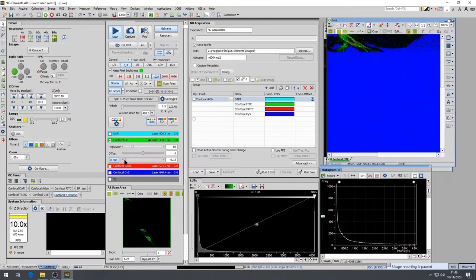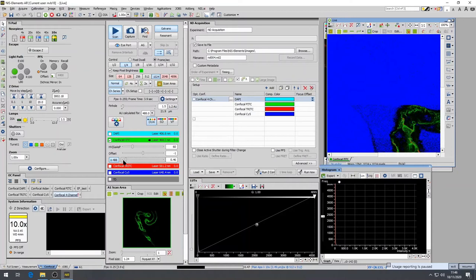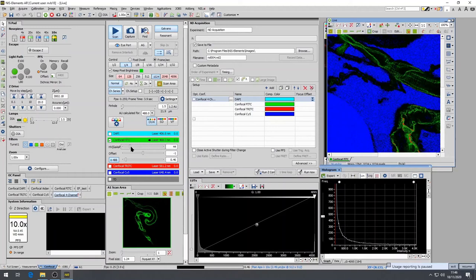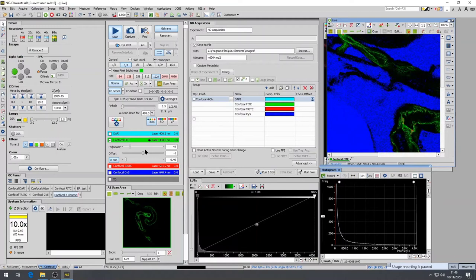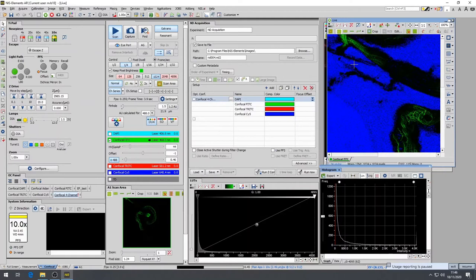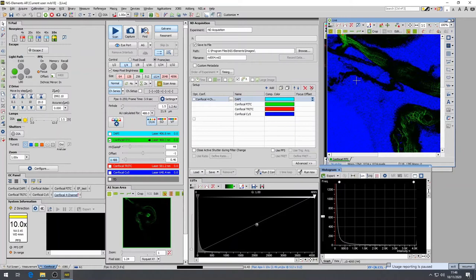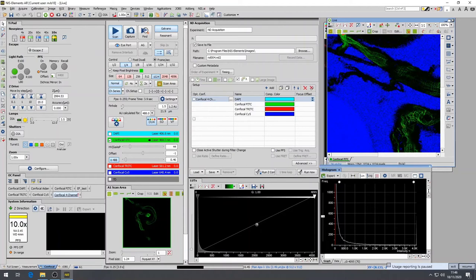At this point, I'm setting up the laser power and gain for the FITC channel. Oversaturated pixels are set to show in red and undersaturated pixels are set to show in blue, as you see in the background. So by reducing the laser power, I'll make sure that I reduce the number of oversaturated pixels. If you see only a few red pixels, that is fine. I also go through the Z stacks a little bit just to make sure that above or below the focal plane that I'm looking at at this point, it doesn't have oversaturation.